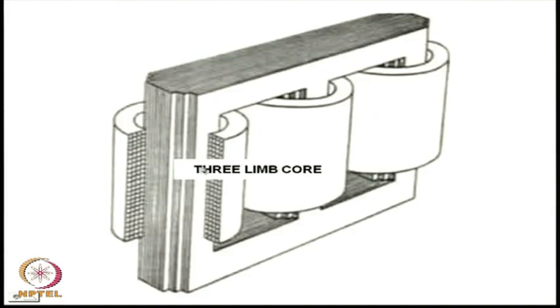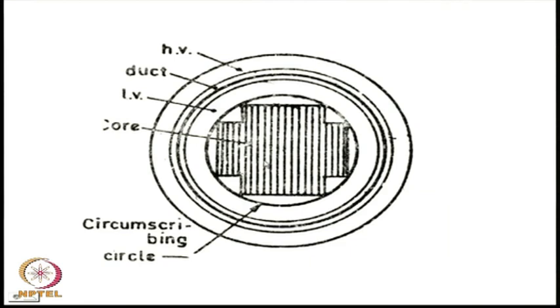If I look at a top view of one of the cores along with the winding, it will look somewhat like this. This part is the actual core cross section on which there is an insulating bobbin cylinder, made up of pressboard or SRBP cylinder. On the cylinder, first the LV winding will be placed, then there will be a gap between the LV winding and the HV winding. There will be a second cylinder on which the HV winding will be placed, and there will be a gap between HV and LV winding through which cooling fluid may be circulated.